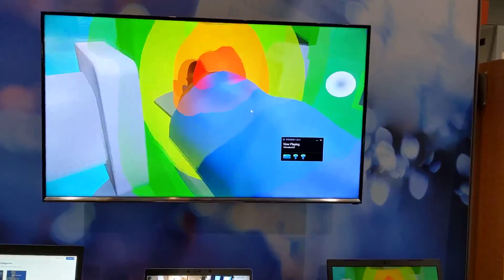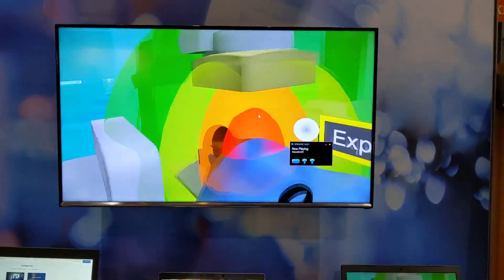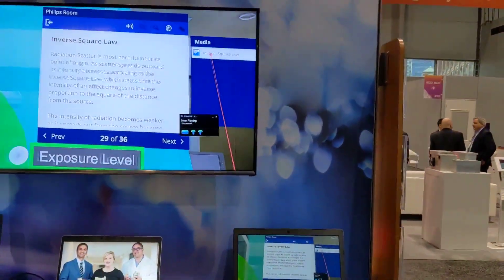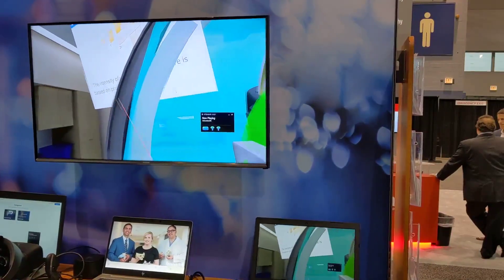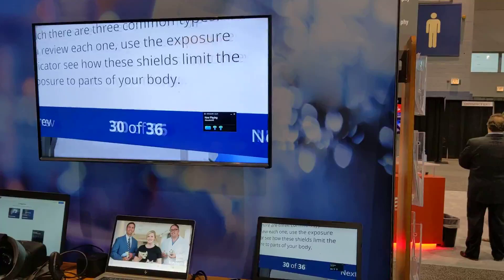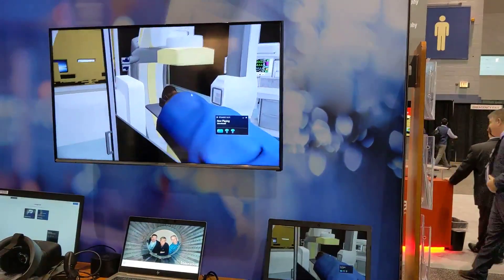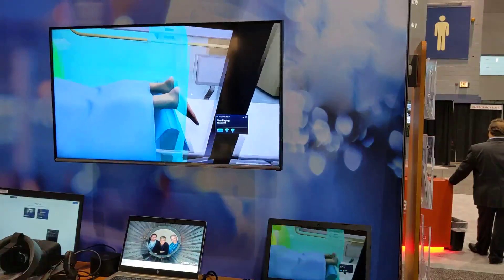Now we've put on our radiation safety devices because we're going to be standing near the x-ray beam. As you walk in, you can see the exposure getting deeper — if I reach my hand in there, I'm getting the highest exposure. We also talk about the inverse square law: the further away you are from the radiation, the better it is, and it's not just a one-for-one relationship. We bring in a lead shield — if you stand behind the lead shield, you can see no x-rays are getting to me.